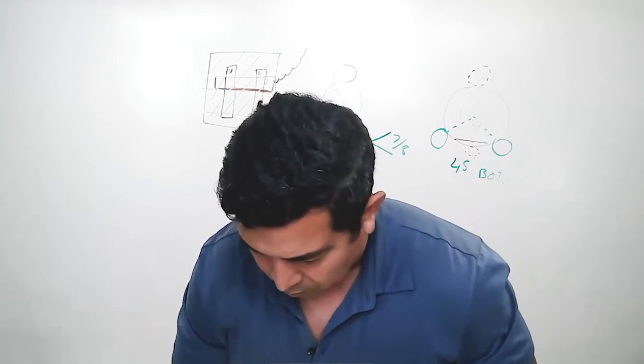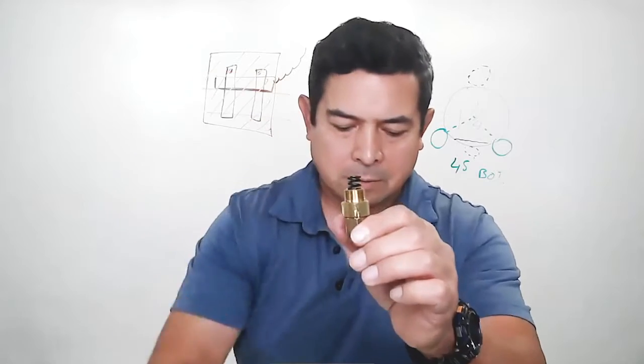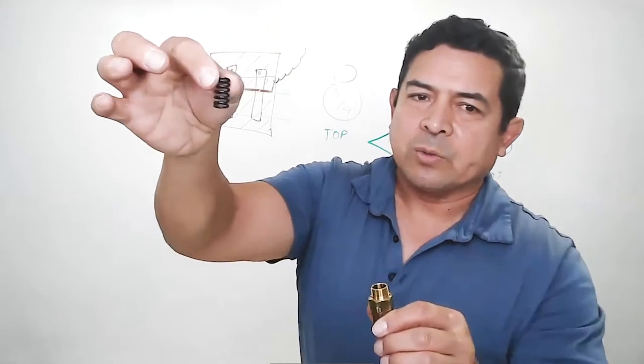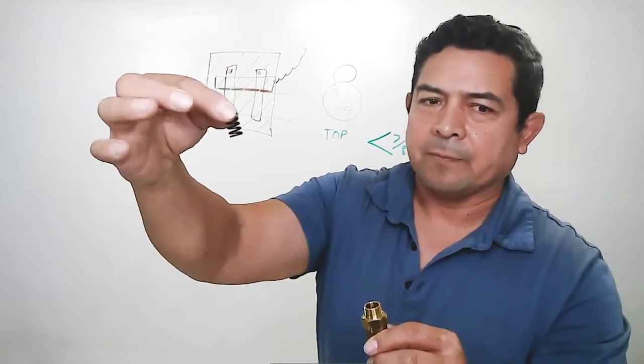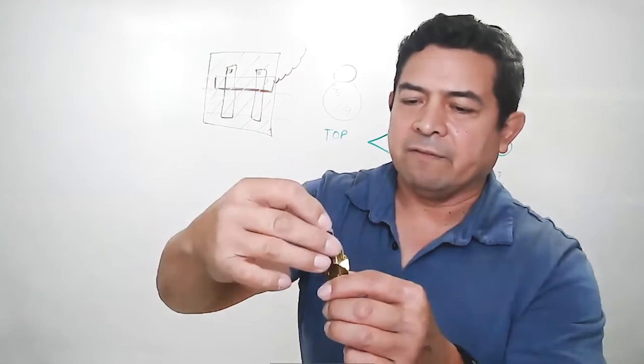Now, once those pins push down on that, it compresses that spring right there. This spring is what they call superheat spring. So this is my superheat spring. And it fits right on up in there. Now at the bottom of this, there's another little brass piece. And that brass piece is adjustable.